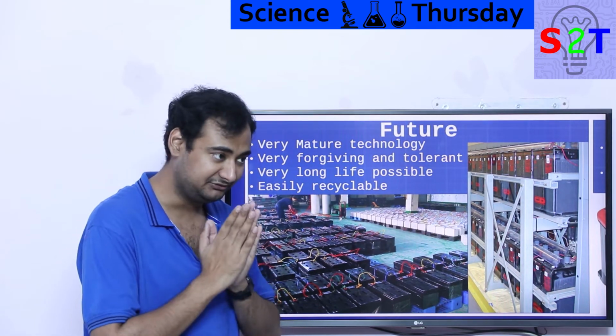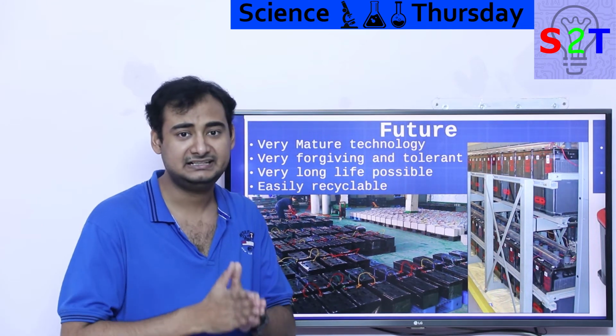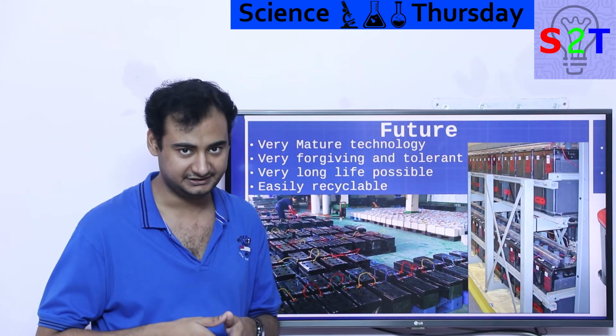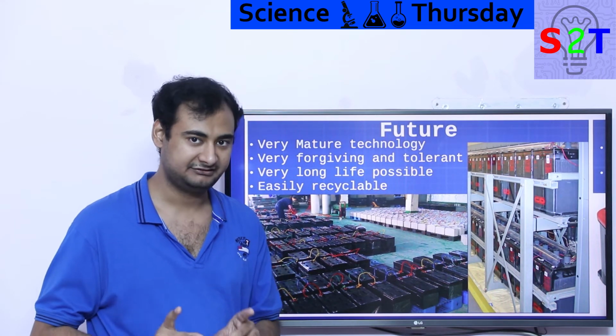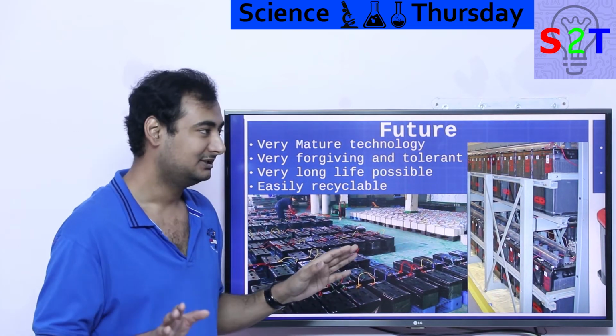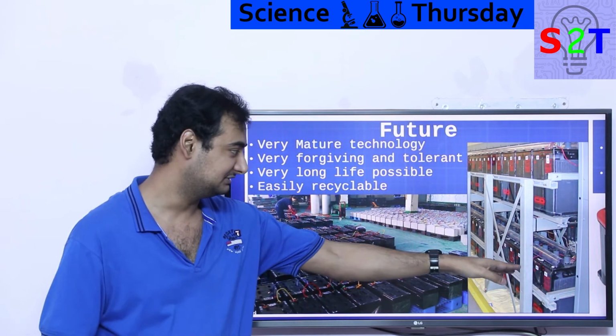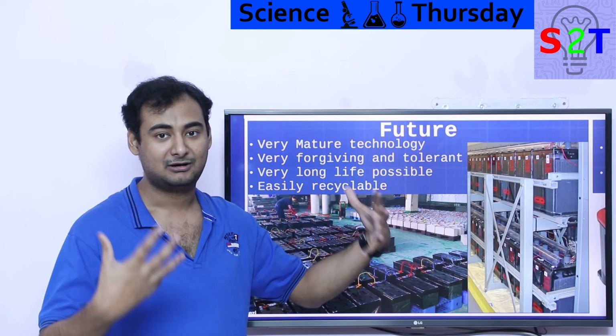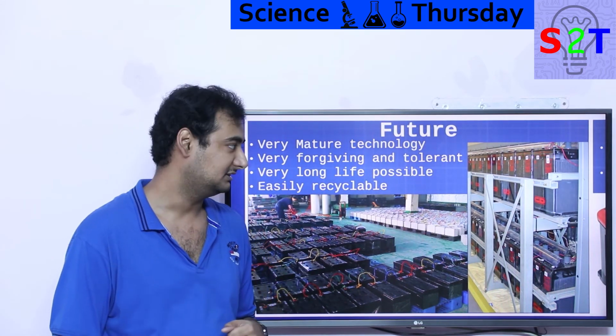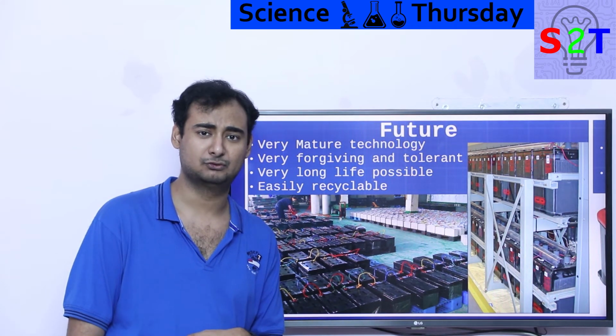So that's why. And if you really can afford it, let's say the batteries that go into submarines, those last a very long time. You can buy Exide batteries which have a warranty of 25 years. That's simple. 25-year long warranty. Again, the plates are huge and thick. Density wise, don't even think about density, nor in terms of power, simply because to get that power oomph, you need thin plates. Thin plates do not last. So if you want to build, let's say, power backup for a server or large data banks, generally people employ lead acid battery with online UPS system. And some systems are as high voltage as 3000 volts.